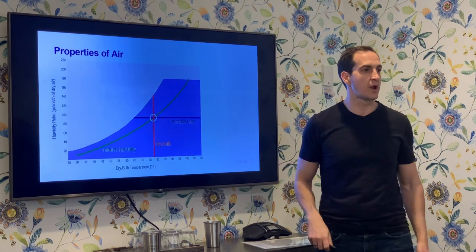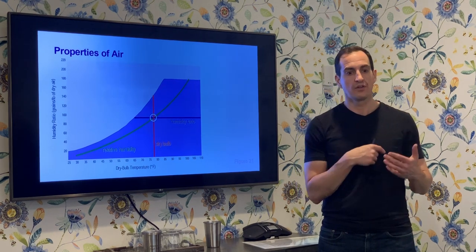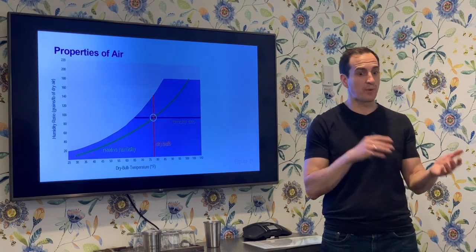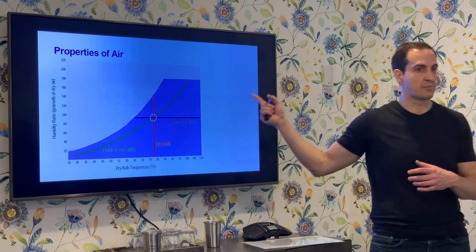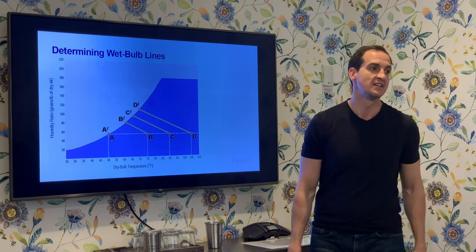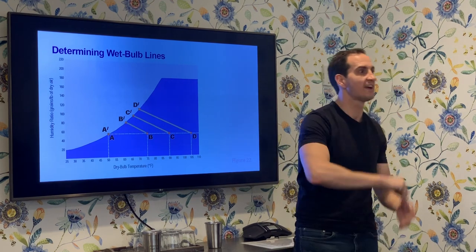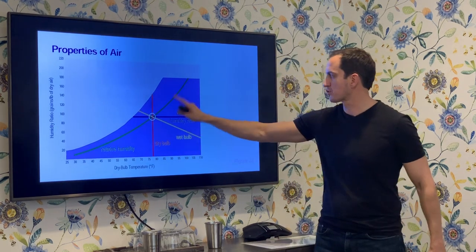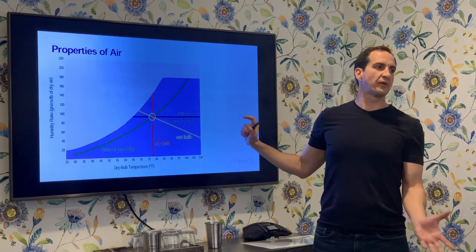We've talked about dry bulb, wet bulb, dew point, absolute humidity, relative humidity, and humidity ratio. There's one more property we need to talk about: as you heat air up, it occupies more cubic feet per pound. So if I'm moving air through a fan at a certain temperature and then cool that air down, I'll be moving heavier air relative to the same volume. The other thing you'll find on the chart are specific volume lines — cubic feet of air per pound of air.